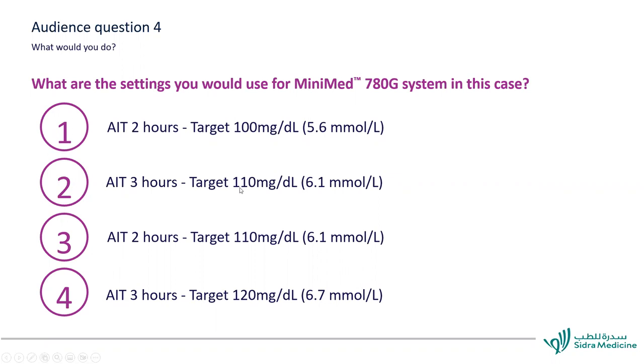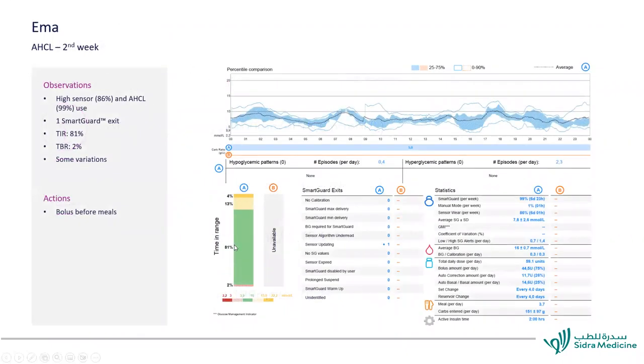Emma's three-month data shows 78% time in range, slightly better glycemic control, no exits, and GMI of 6.8. At six months, she was using the Guardian 4 sensor at 86% with almost no exits. Now almost a year with the 780G, just in the first week with optimal settings we achieved more than 80%, and this 80% was maintained over the same period. No hypoglycemic events. A1C decreased below 7 and stayed below 7 — the last GMI is 6.5 at month 11. The system settings were never changed; the only change was the carb ratio from 6 to 5, with immediate improvement in glycemic control.